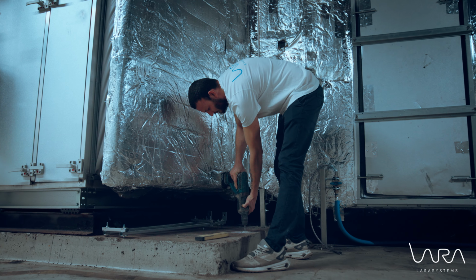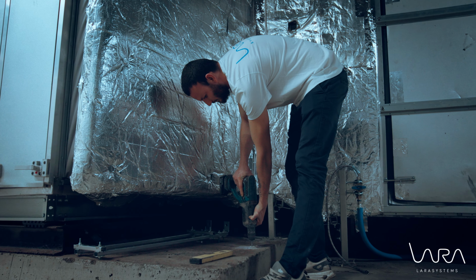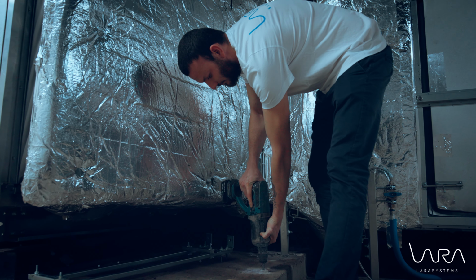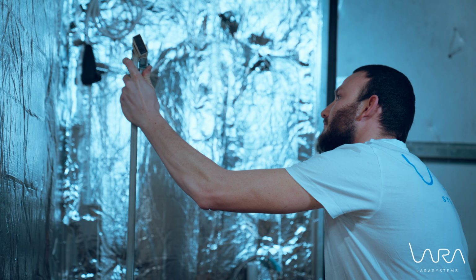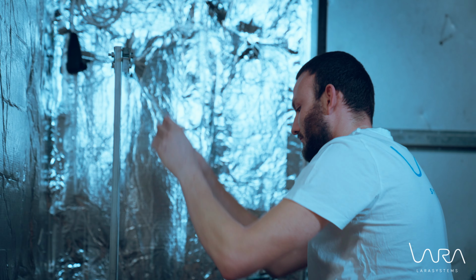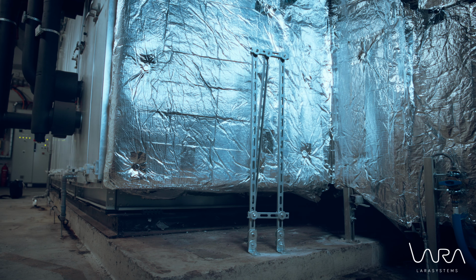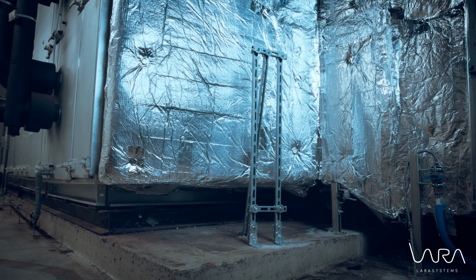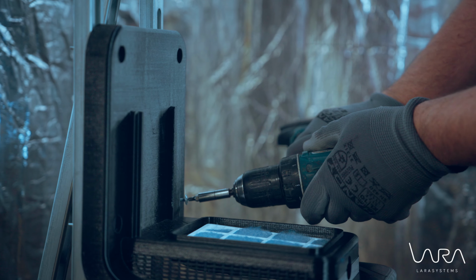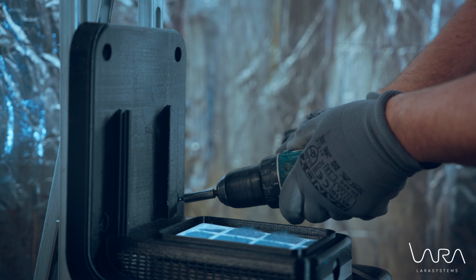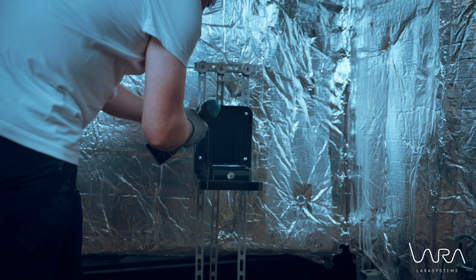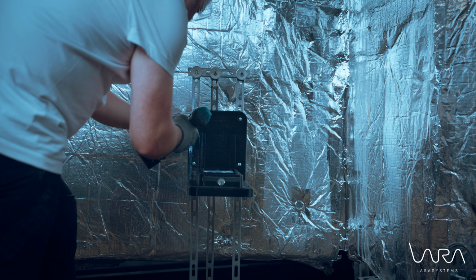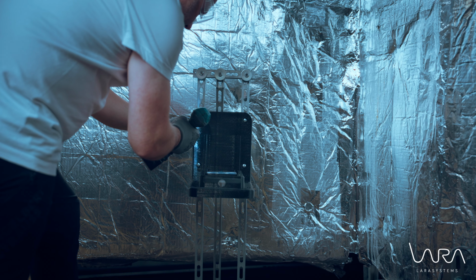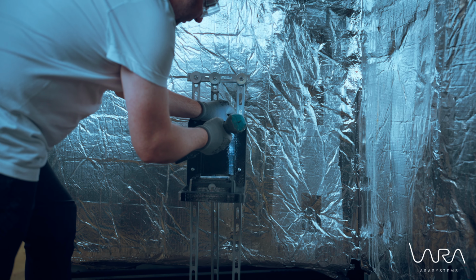First, let's look at mounting on the support stand, which we also used here on site. First, firmly secure the support stand to the designated location. Ensure that the stand is perfectly horizontal, stable, and that the device cannot shift during later use. Next, attach the base belonging to the device onto the support structure. The Lara Systems device must be slid onto this base, into its place.